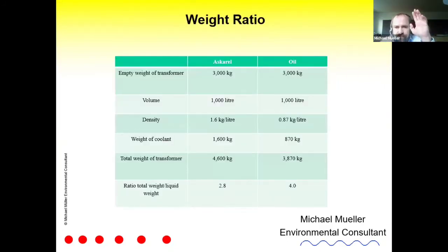Weight ratio. The same transformer, one is filled with Askarel, the other one with oil. The empty weight of the transformer is 3 tons, 3,000 kilo. The volume is 1,000 liter. If you fill the transformer with Askarel, 1,000 liter is 1.6 tons. 1,000 liter of oil is 870 kilo. So we add total weight, empty weight plus liquid weight. In case of Askarel, we have 4,600 kilo.